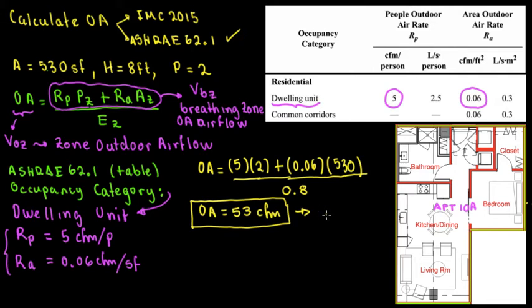Alright. So in other words, in order to comply for the minimum outside air requirements or fresh air ventilation rate for this unit living or dwelling unit, apartment unit, you have to have at least 53 CFM. But now you may wonder, why, Rumberto, in the previous video, you had the same unit layout, but you obtained another number, which was like 38 CFM. So that depends on the jurisdiction. So every client, every building owner, they will let you know what the county requires. They require you to use IMC 2015, 18, 2021, or they require you to use ASHRAE 62.1, 2010, 2013. So they're going to give you the guidelines. Based on that, then you're going to design how much outside air you need.